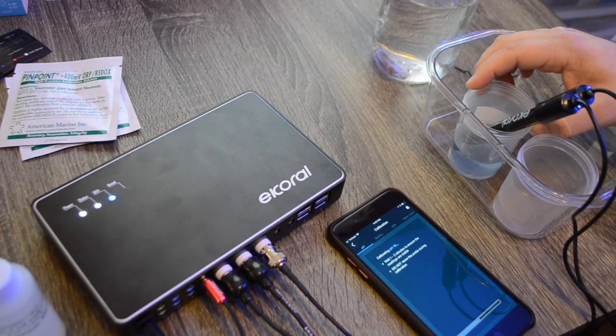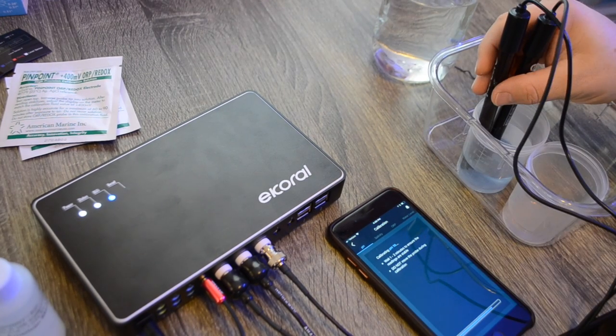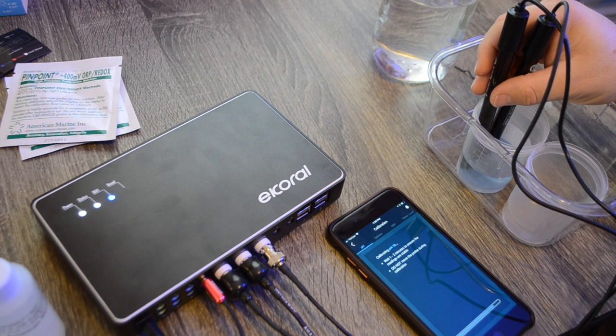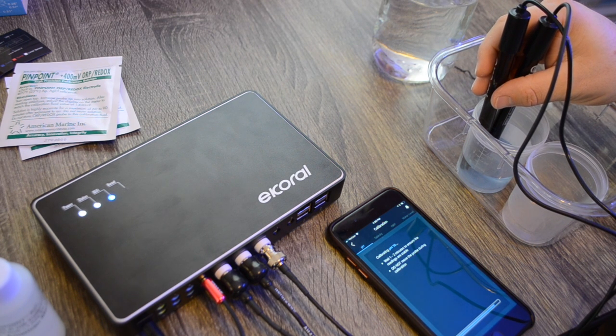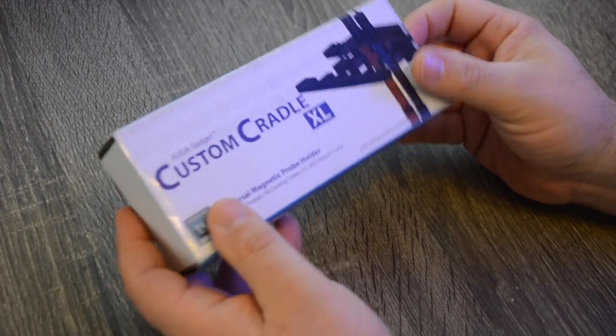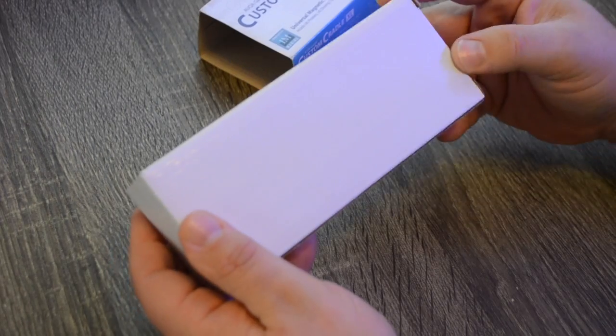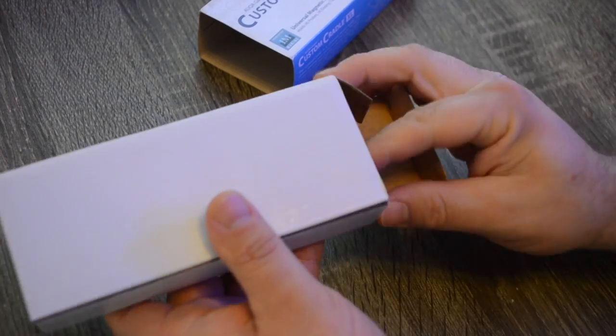But something that you're not going to see me do in the calibration process was drying off the probes, because I was doing that behind the camera and didn't really want to be shaking off fluid all over the eKoral as well as my cell phone. But overall, the process of calibrating the probes was pretty painless and easy. You basically click on the tab of the probe that you want to calibrate, and it gives you step-by-step directions how to calibrate that individual probe.